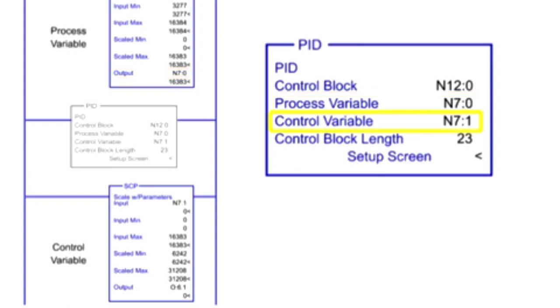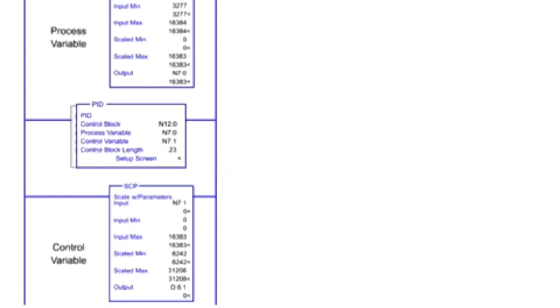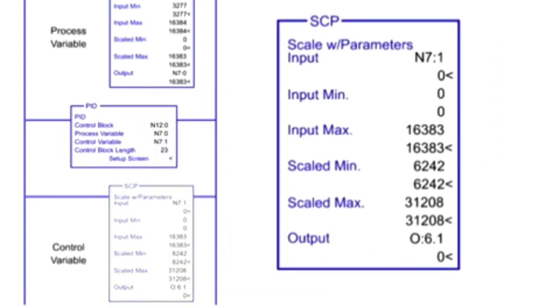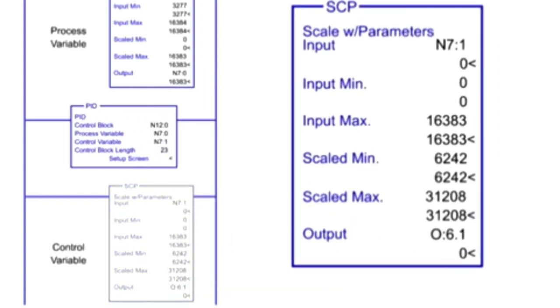The control variable parameter is programmed as an integer, which is the memory address for the output value. Next, the control variable range of 0 to 16,383 is scaled to an analog output module using the second Scale with Parameters instruction.